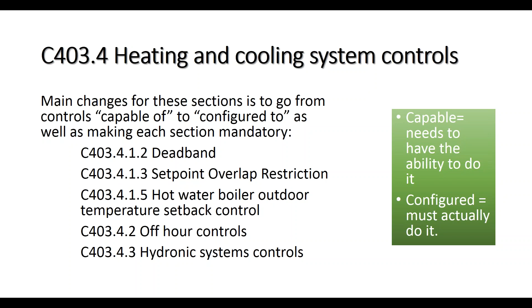The other change is that it clarified these controls are mandatory -- they're not something you can trade off, not something you can leave out. We're not going to mess with mechanical equipment controls itself, that's the mechanical section of the code, the IMC. But what we are going to do is provide controls to shut it down when we don't need to use it as much, sequence the operations, have controls that can shut them down when they're not needed as much.